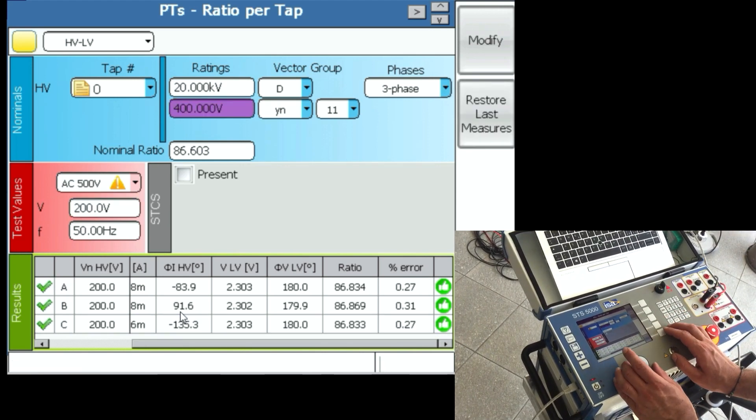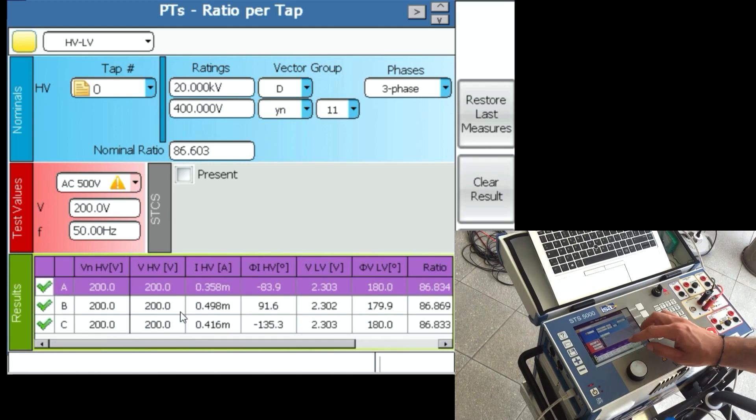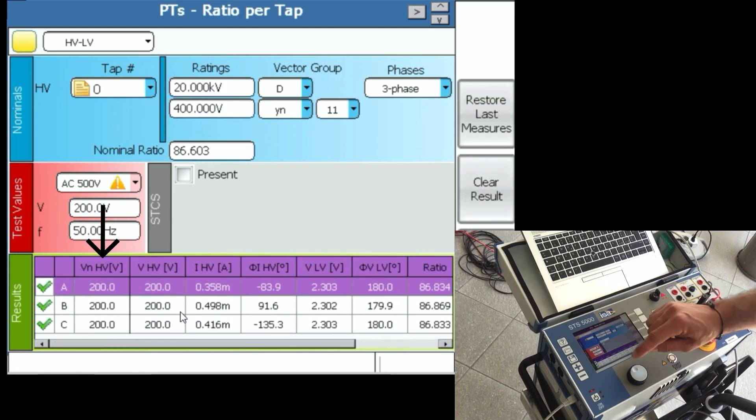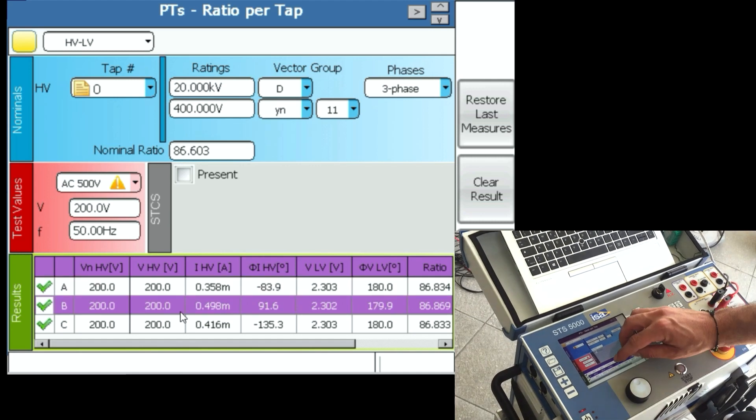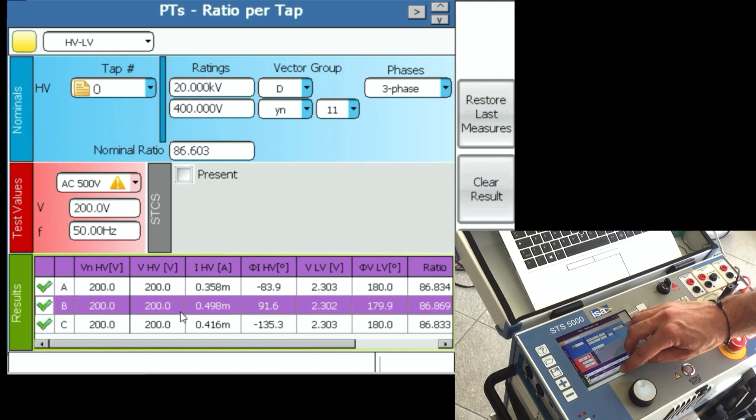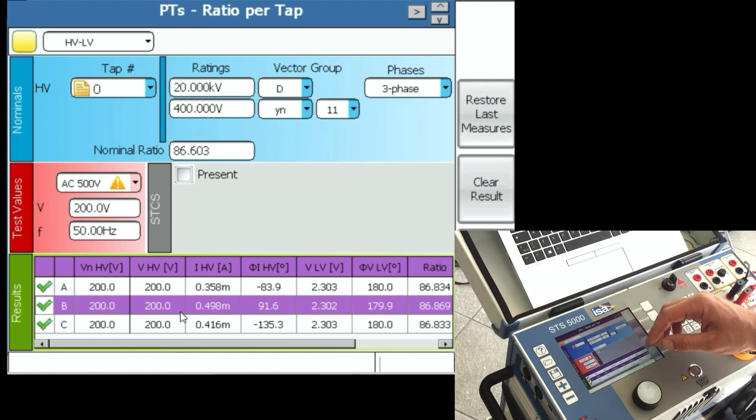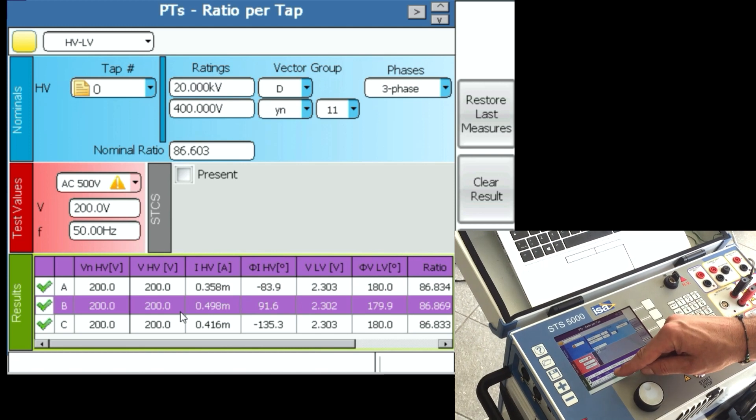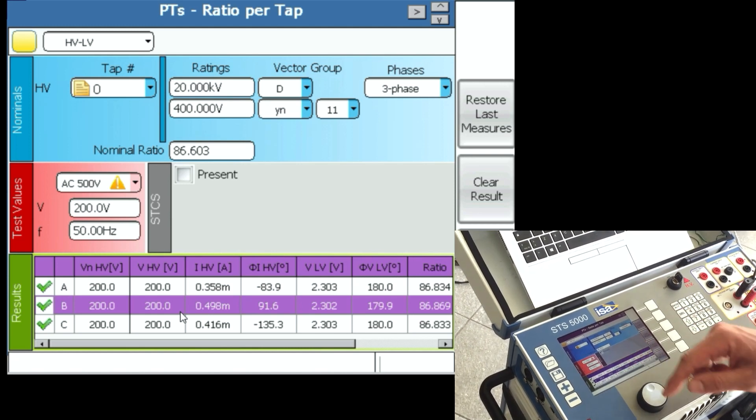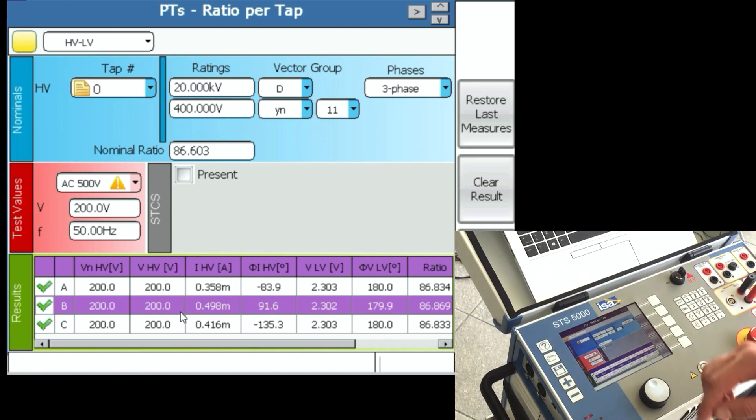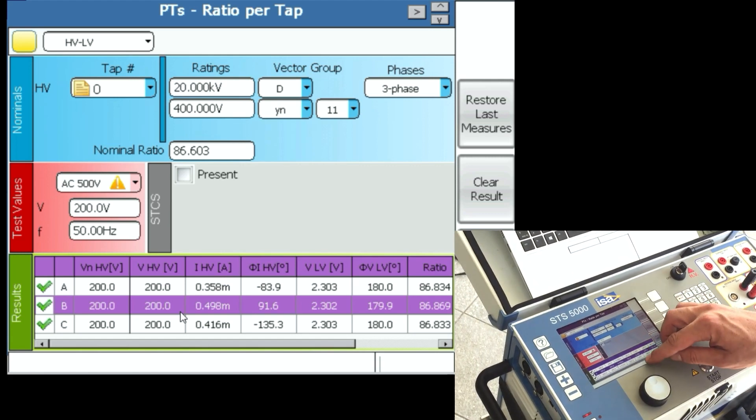Now we can see the full result right here. So I go down, scroll columns. We generated for all three phases 200 volts. The current coming inside was this, is the result of no-load test. And actually let me tell you, it looks good because the middle current is higher than the ones in phases A and C.